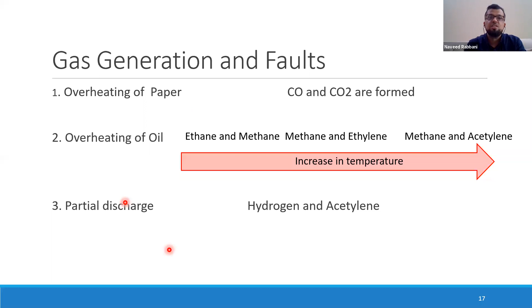Gases shift from ethane and methane to methane and acetylene in higher concentrations. And for partial discharges, hydrogen and acetylene are produced in relatively larger quantities. You can see a graph here, and you can see that for partial discharge, at the start, hydrogen is generated in relatively higher concentration. First of all, let me tell you about the axes. The x-axis tells you about the fault types. The y-axis tells you about the relative fault concentration.